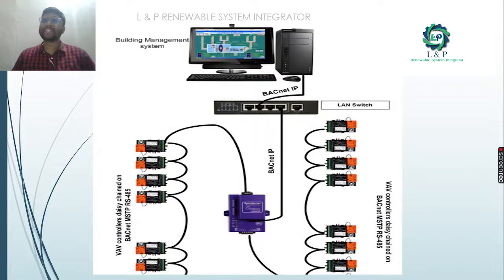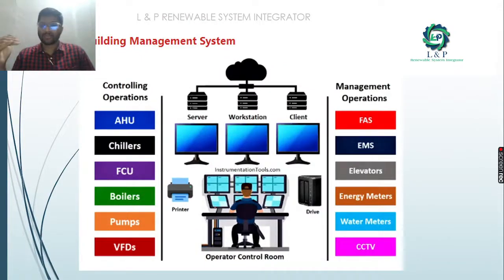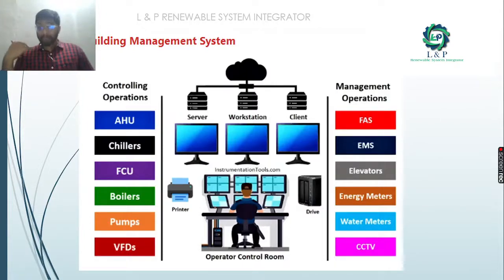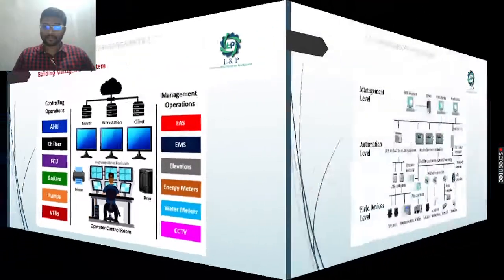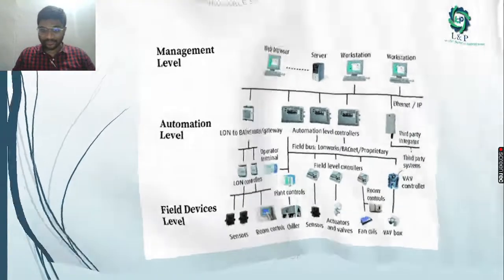This is a simple application showing how it is established in a building management system using BACnet IP with VAV field devices. A BMS includes a server, workstation, client, and operator control room. You can perform control operations for air handling units, chillers, fan coil units, boilers, pumps, VFDs, fire alarm systems, escalators, elevators, energy meters, water meters, and CCTVs. The network is classified into three levels: management level, automation level, and field panel network. BACnet routers are needed between the field panel network and the automation network.